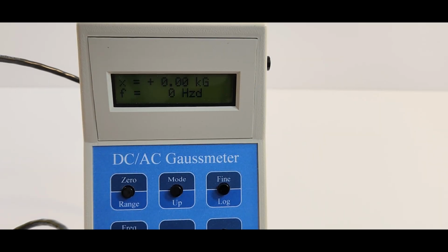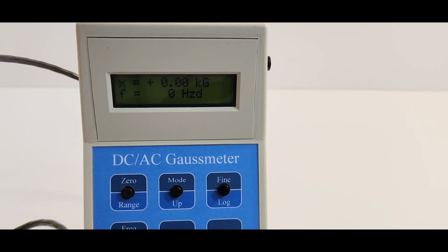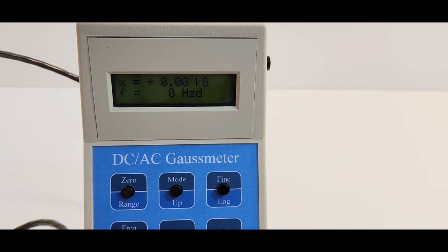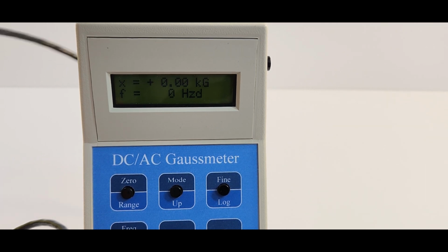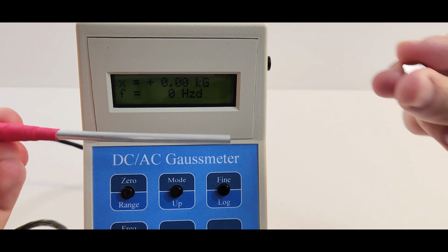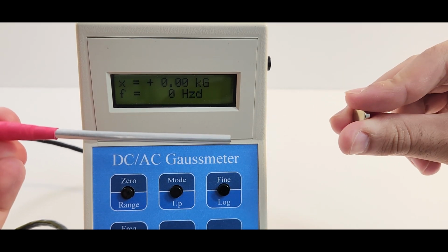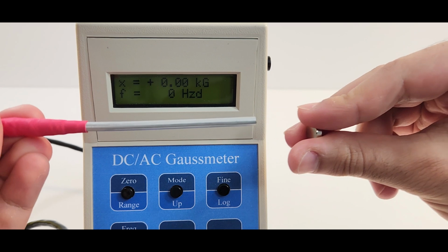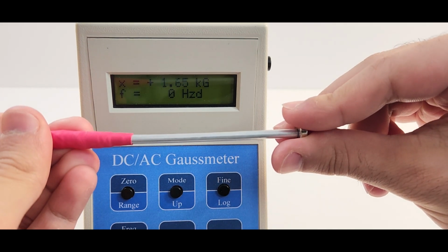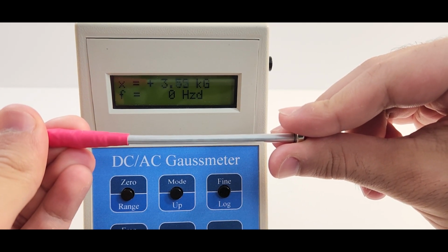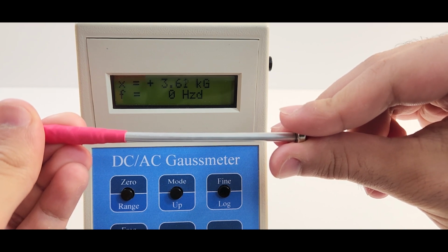Now, let's do a demonstration. Given that we zeroed the meter and set the range to kilogauss, we can now perform a measurement using this axial probe. Here is a magnet measuring just above 3.5 kilogauss. Placing the probe at 90 degrees, or perpendicular to the surface of measurement, you'll get the maximum measurement value.